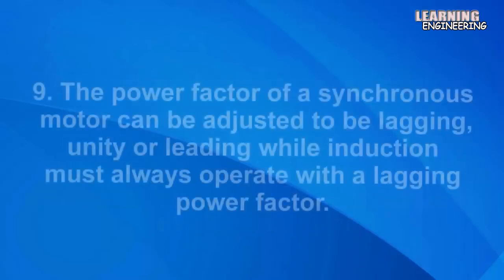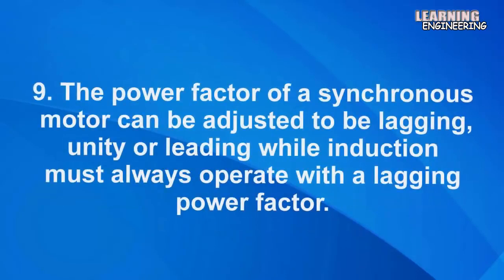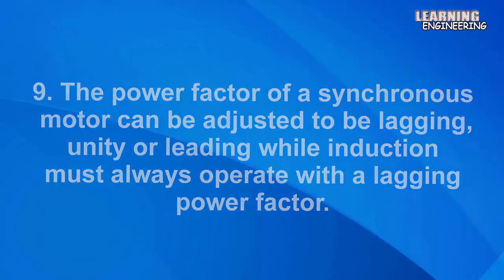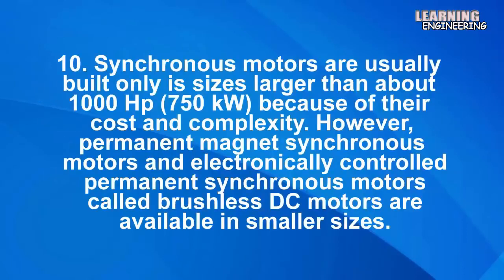Nine, the power factor of a synchronous motor can be adjusted to be lagging, unity, or leading, while induction motors must always operate with a lagging power factor. Ten, synchronous motors are usually built only in sizes larger than about 1000 horsepower (750 kilowatt) because of their cost and complexity.